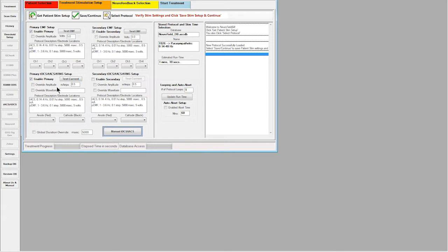So here in the Bay Area, I know I have very many sensitive clients. So I override and I start really low. I start at 0.1 milliamp. And if I need to, I'll go up from that, but that's where I start.